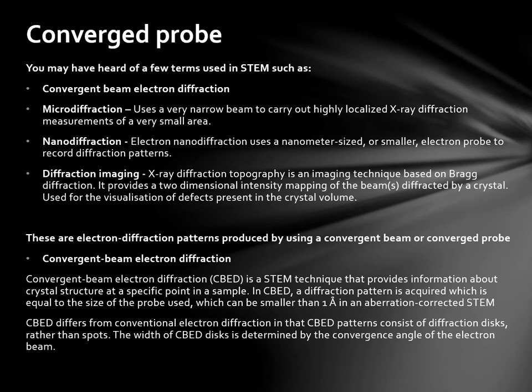Then we have the convergent beam electron diffraction. CBED is a STEM technique that provides information about crystal structures at a specific point in a sample. In CBED, a diffraction pattern is acquired which is equal to the size of the probe used. CBED differs from conventional electron diffraction in that CBED patterns consist of diffraction disks rather than spots. The width of a CBED disk is determined by the convergence angle of the electron beam.